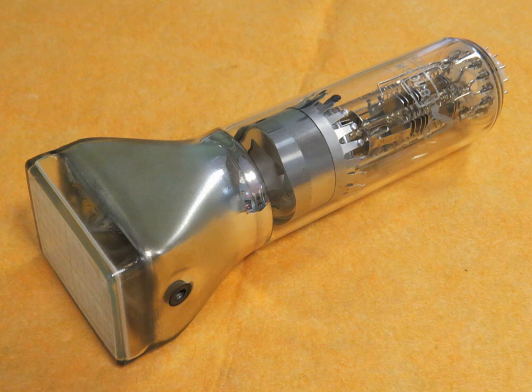Topic: horizontal position control. The horizontal position control moves the display sidewise. It usually sets the left end of the trace at the left edge of the graticule, but it can displace the whole trace when desired. This control also moves the XY mode traces sidewise in some instruments, and can compensate for a limited DC component as for vertical position.